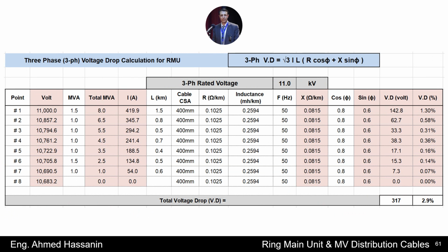In the third table, I will explain how to use this table to make the individual voltage drop for any part of the medium voltage cables of the ring system, and how to make the total voltage drop for any ring system with any numbers and the values of distribution transformers and any numbers of medium voltage cables. Also, I will explain how to change any data in this table according to your project. In addition, I will attach this Excel sheet with my course.